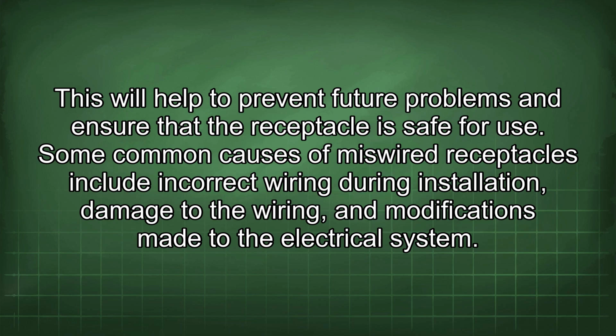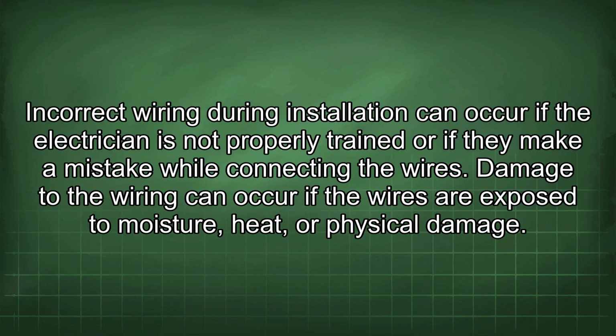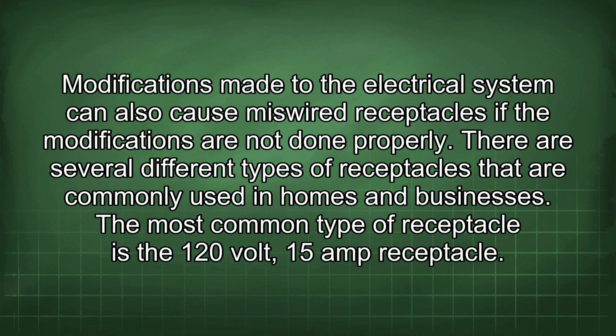Some common causes of miswired receptacles include incorrect wiring during installation, damage to the wiring, and modifications made to the electrical system. Incorrect wiring during installation can occur if the electrician is not properly trained or if they make a mistake while connecting the wires. Damage to the wiring can occur if the wires are exposed to moisture, heat, or physical damage. Modifications made to the electrical system can also cause miswired receptacles if the modifications are not done properly.